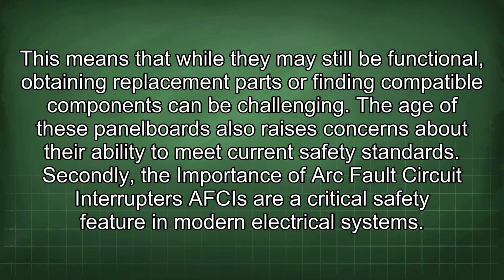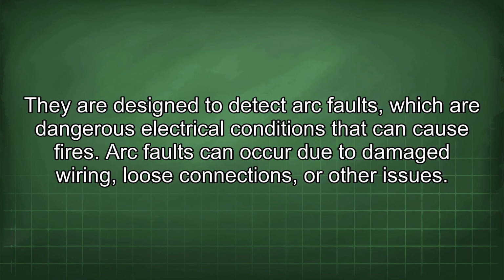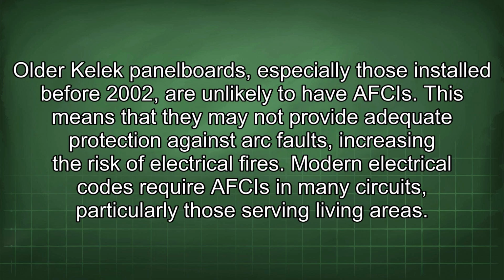Secondly, the importance of arc fault circuit interrupters. AFCIs are a critical safety feature in modern electrical systems. They are designed to detect arc faults, which are dangerous electrical conditions that can cause fires. Arc faults can occur due to damaged wiring, loose connections, or other issues. Older Kelek panelboards, especially those installed before 2002, are unlikely to have AFCIs. This means that they may not provide adequate protection against arc faults, increasing the risk of electrical fires.